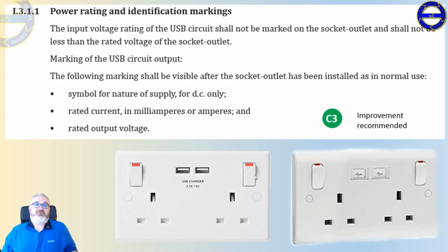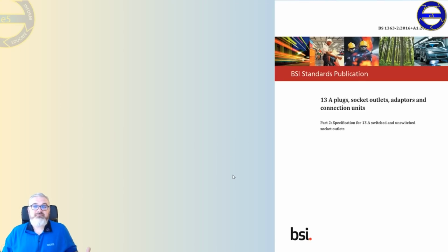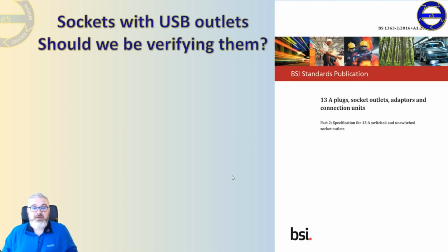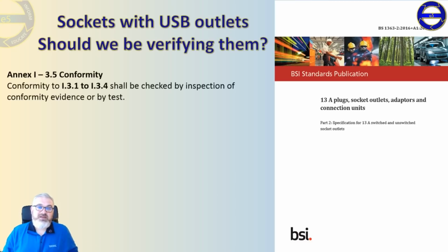So the next thing I did with USB socket outlets was look at the standard again and ask the question, should we be verifying them? Now let's go back to the bit at the start, Annex I, section 3.5, conformity. Conformity to 3.1 to 3.4 shall be checked by inspection of conformity evidence or by test. Are we getting conformity evidence from the manufacturers? No, we don't really get it. We get a statement that they conform, but we don't get evidence of it. And do we test it? Henceforth, how would we test it?